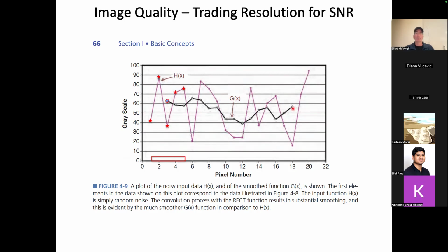When you present the image to a radiologist, they look at it and say, I can't look at that. This is garbage because it's got too much noise on it. It's all speckled and noisy. You can say, well, I'll smooth it for you. You put on a filter that does this kind of averaging, and a lot of the noise goes away. But fine features also go away. If you're looking for a fine feature, it could be averaged away. However, bar none, on the CT scanners we have right now, radiologists always want you to smooth the data as opposed to see it at full resolution.